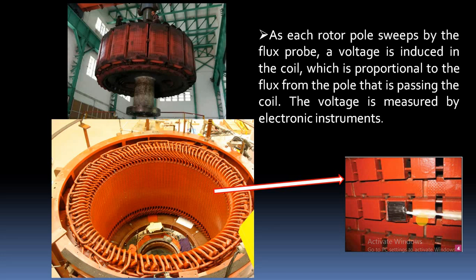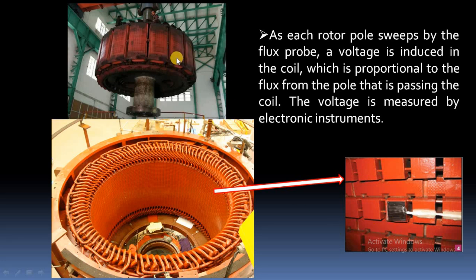The operation principle is straightforward: we glue the probe on the surface of the stator core. The rotor rotates inside the stator, and whenever each pole passes through this probe, the flux generated by that pole cuts the probe turns. A proportional amount of voltage is induced in the probe, which is displayed by the electronic instrument.